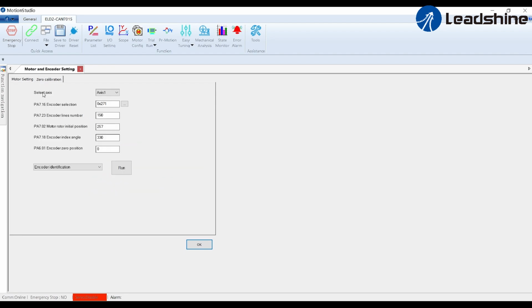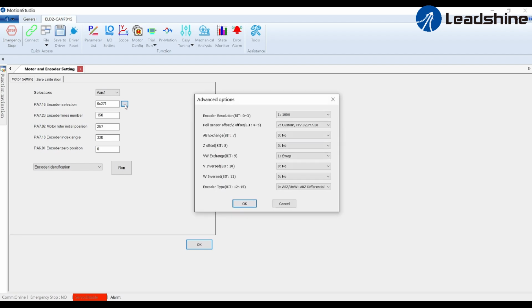First, click this icon behind the PA716 encoder model. Then, according to the motor encoder parameters, select encoder resolution and encoder type. In this video, the encoder is 1000 lines with Hall sensors and the signal is ABZ differential signal, so I select 1, 1000, and 0, ABZ differential. Finally, click OK.